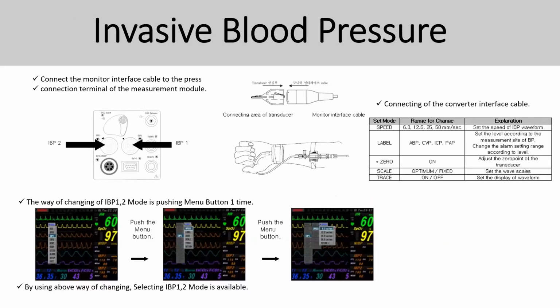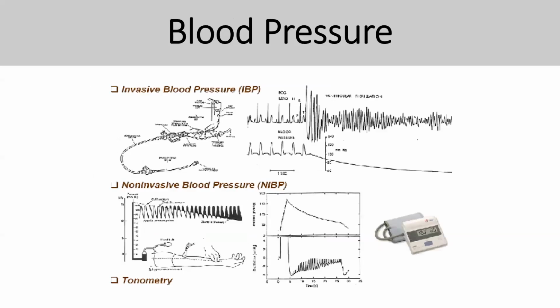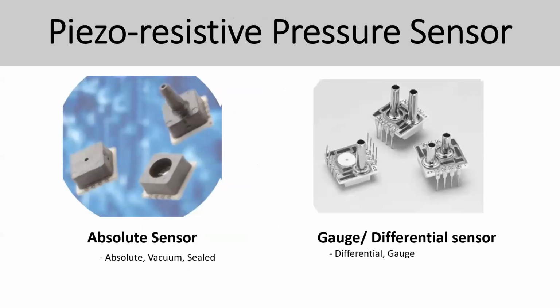Invasive blood pressure is basically one of the most accurate, where you go through the catheter line and all that. So it's going to use a pressure sensor, more accurate, and it is going to capture directly on your line. So this is the comparison between blood pressure, NIBP and IBP. This is how the signal looks when you monitor on the patient. These are basically the sensors that you're going to see in NIBP and IBP as well. You've got differential and absolute sensors, all that.